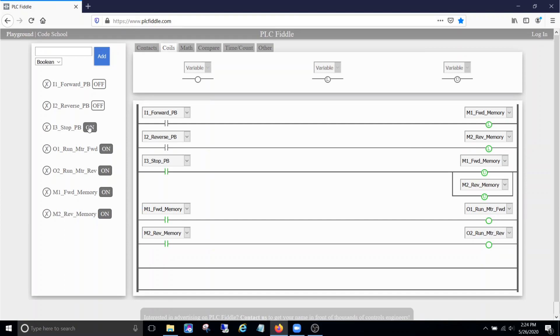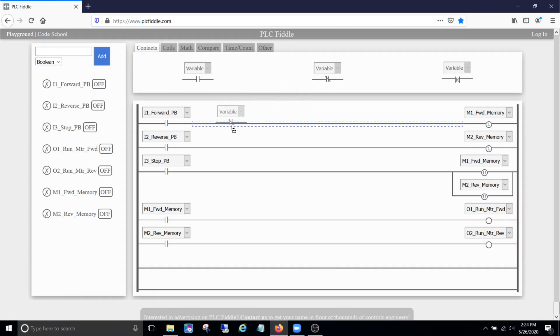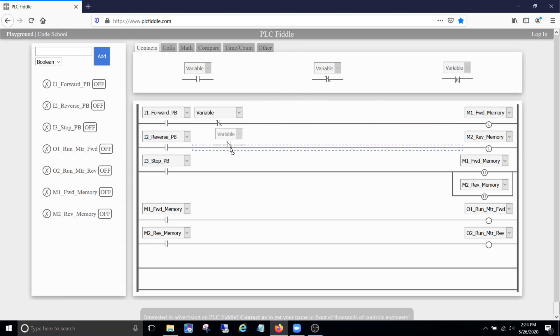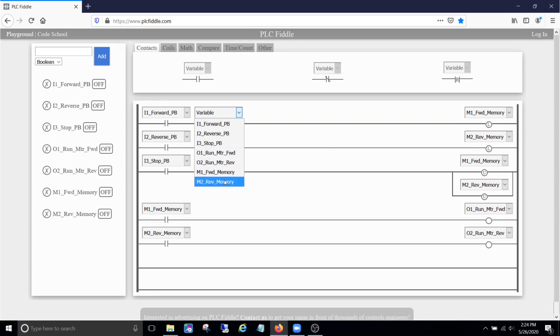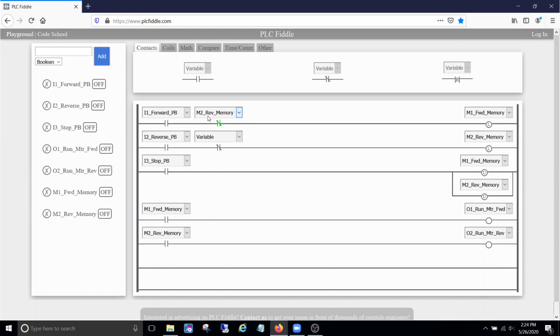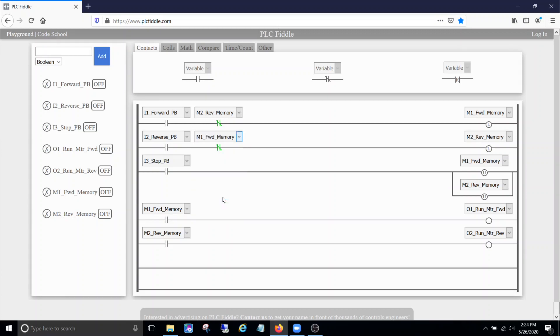So let me press stop. Stop them. And the way that we solve this problem is we're going to drop a normally closed contact in each one of these memory rungs. And for the forward memory coil, I'm going to interlock it with the reverse memory. And for the reverse memory, I'm going to interlock it with the forward memory. So right here, whoever comes on first, forward or reverse, is going to win.